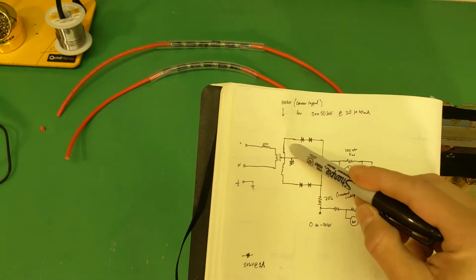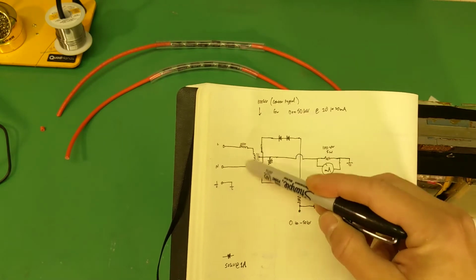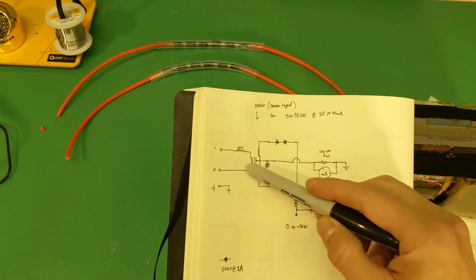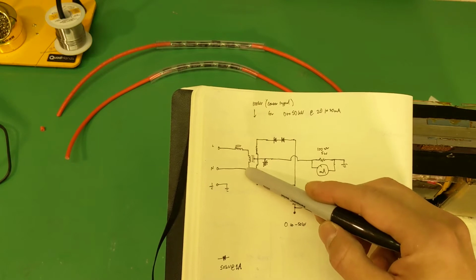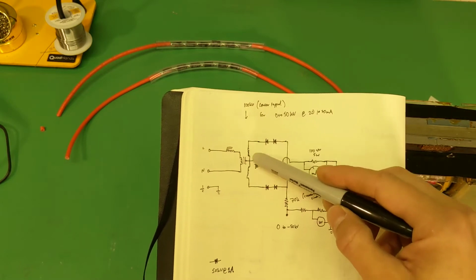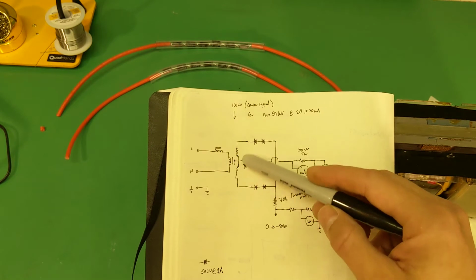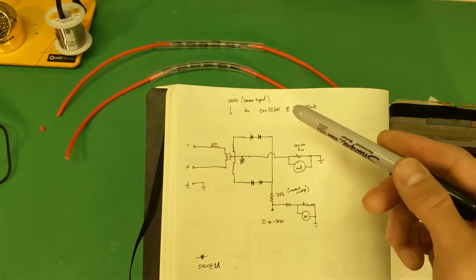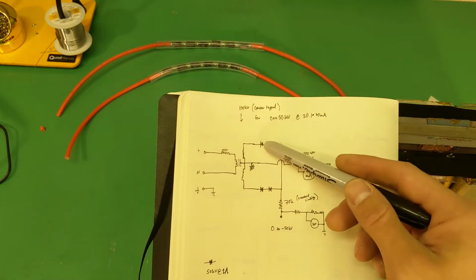This component here is our X-ray transformer. You'll have a primary winding which accepts 120 volts AC input, and we're hoping to find two secondary coils on that transformer, each making about 50,000 volts.